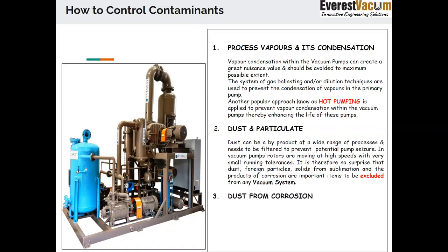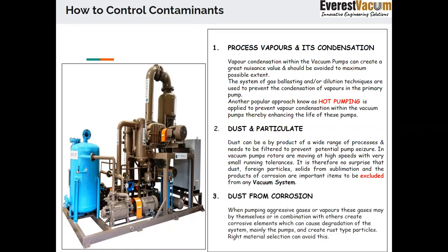And third is the dust from corrosion. It is basically the proper selection of the material of construction, because if it is not compatible in certain applications, like mild steel or SS304 is not compatible, then we need to go in for a higher grade of material. We need to check whether it's compatible or not. So accordingly, the material of construction has to be selected to avoid the dust from corrosion.